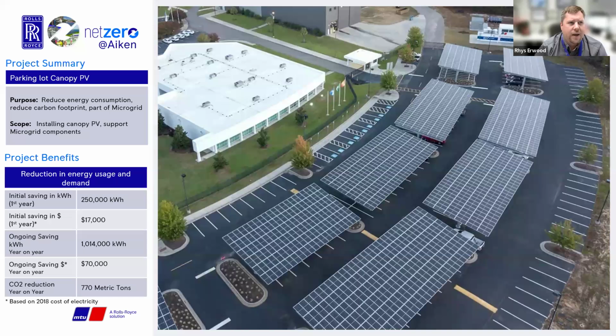Using the microgrid and the PVs, we take the power we generate from the PVs and store it in our battery container. During the day we charge the battery container, then switch over to PV. That helps shave the peak off and reduce our top-end costs, and we can then leverage the battery over a more extended period into the late evening when PV generation starts to drop down.